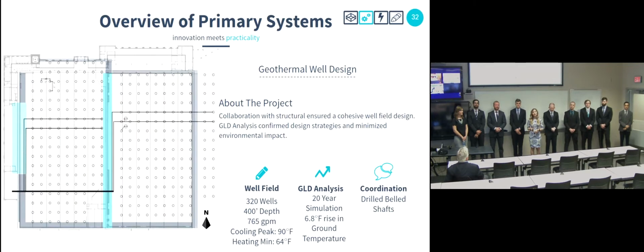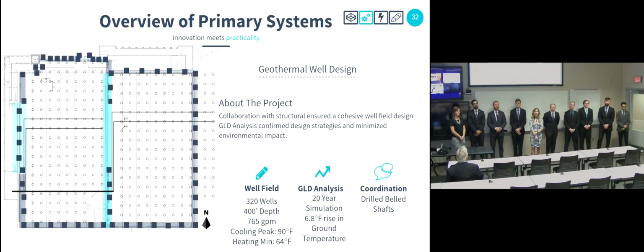This geothermal well field consists of 320 wells, roughly 400 feet deep. A GLD analysis did take place to make sure there was proper sizing of the well field, as well as to accommodate ground temperature rise over a 20-year span. Coordination with structural took place to ensure that the well fields did not interfere with their drilled shafts. As you can see, we were able to locate our well fields in a way that did not interfere and will help move along the construction process that will be touched on later.